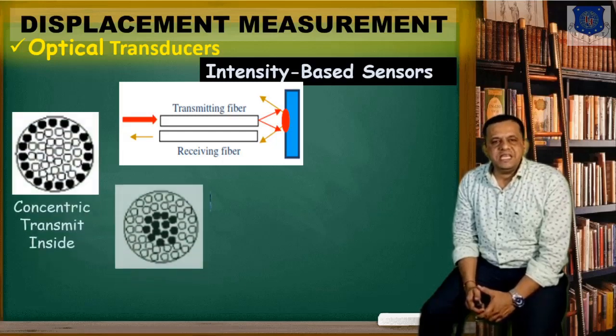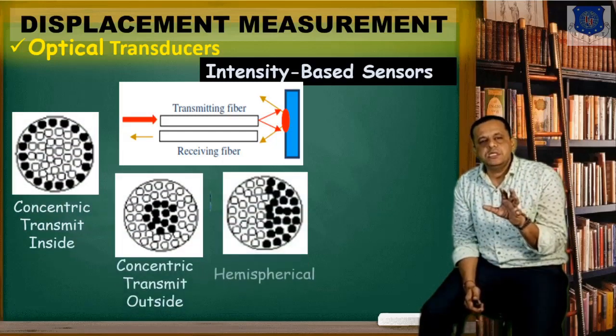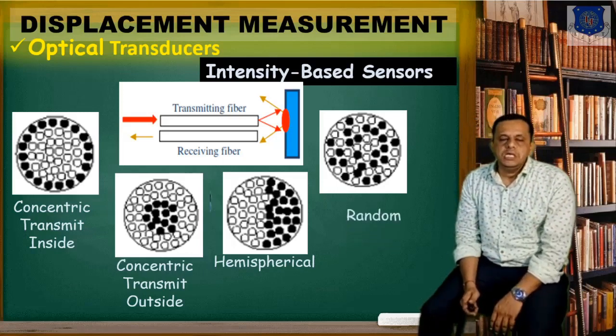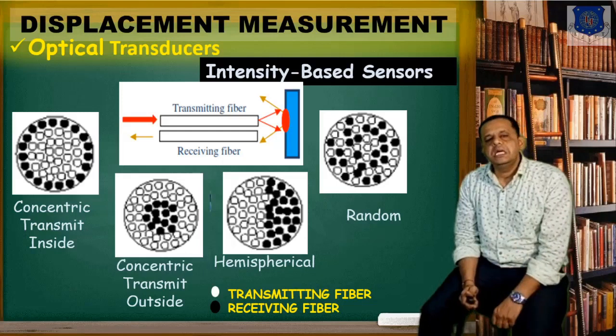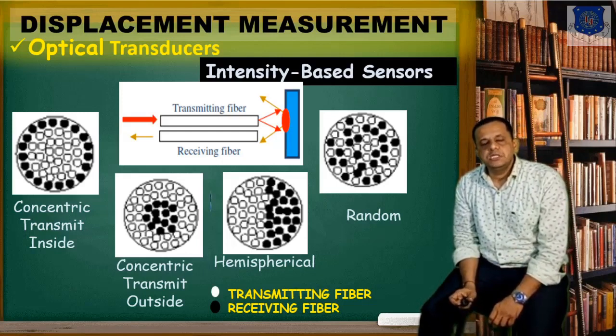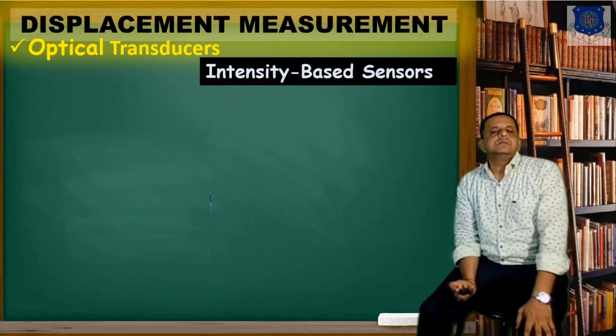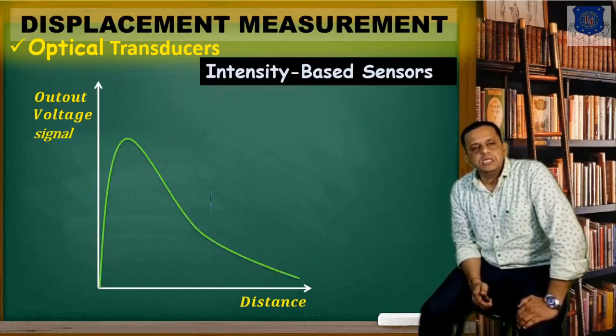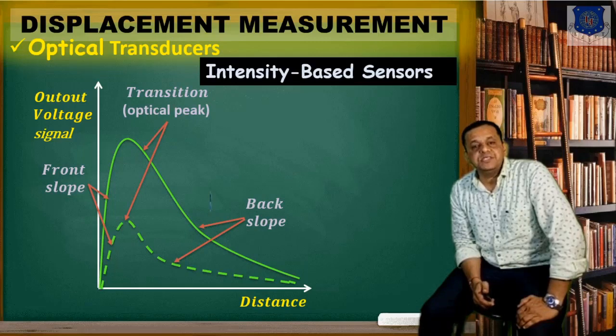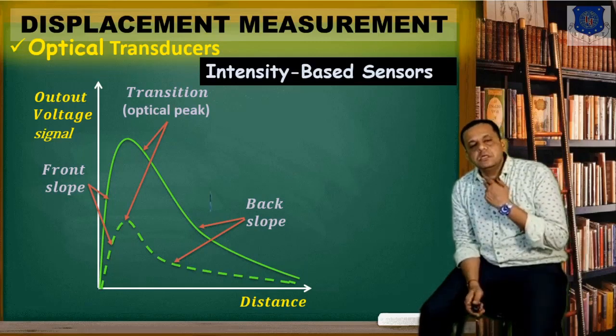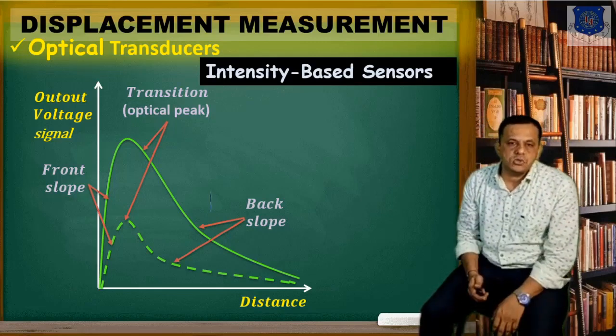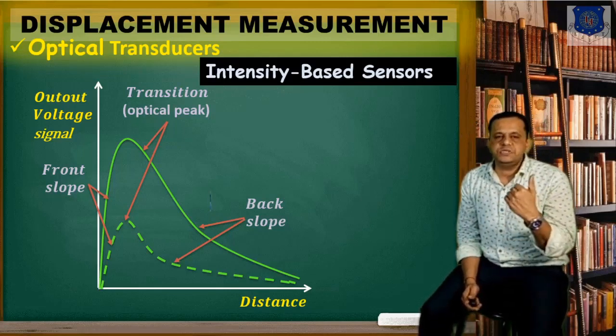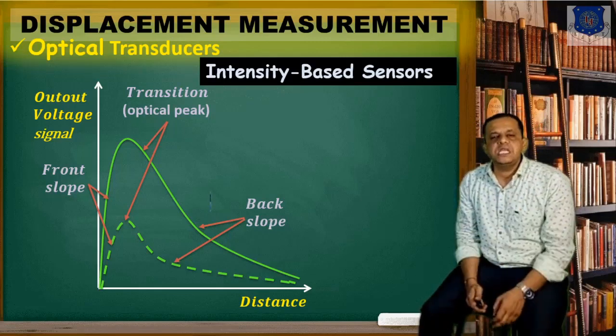Looking at the diagram, there are different fiber topologies: concentric transmit inside, concentric transmit outside, hemispherical, and random. The black spots represent receiving fibers and white spots are transmitting fibers. A transfer factor is generated, and the output voltage versus distance has a characteristic curve with a maximum optical peak in the middle portion, along with a back slope and front slope. The output signal is directly converted from the light intensity received by the detector.